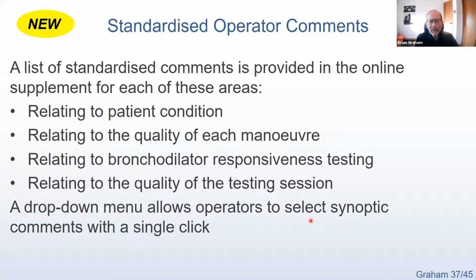Another option that we had in here was the standardized operator comments. And in the online supplement, we've got a full list of standardized operator comments in each of these areas that relate to the patient condition, that relate to the quality of the maneuver, the bronchodilator responsiveness testing, and the quality of the session as a whole. And the idea here is that there would be a drop-down menu at particular times during the maneuver where the operators would simply select a comment with a single click. And if everything went well and you don't need to enter any comments, it's one click to say no comments. And this makes it a lot easier for the operator because now the comments are standardized and they're synoptic. You're not writing stories, you're picking out specific details. And that's an important part of it.